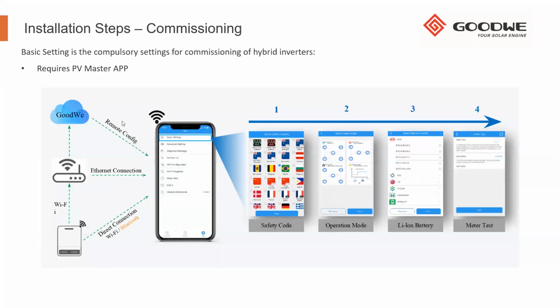We then open the PV Master application. That will scan for inverters. We can select the inverter and then browse to the settings page. In here, it will ask us for a password. That password is GoodWe 2010, all lowercase.